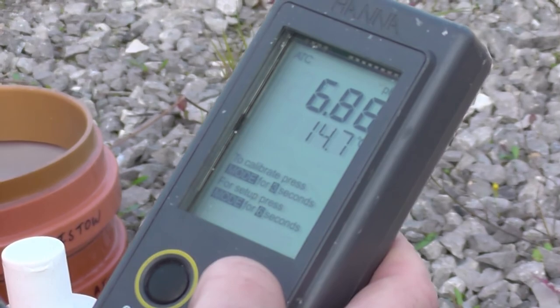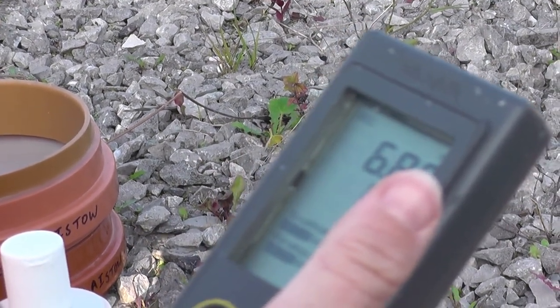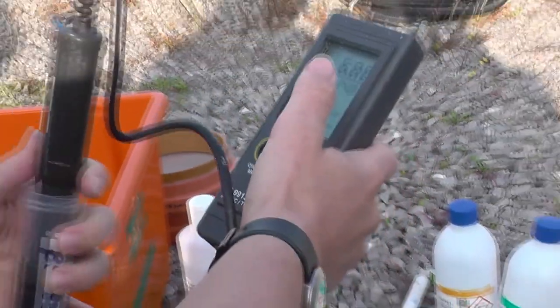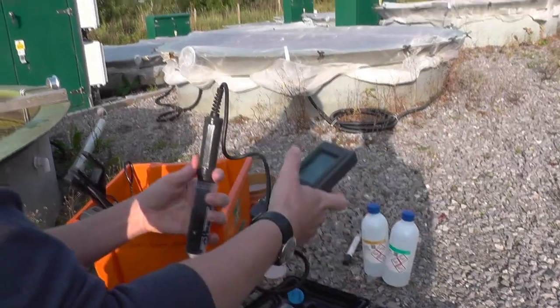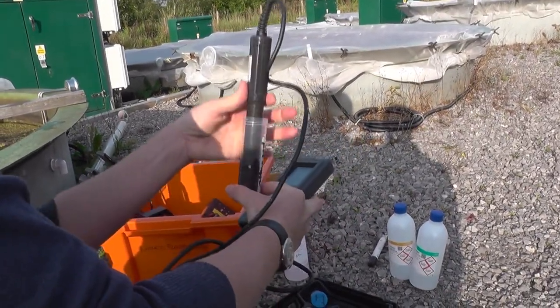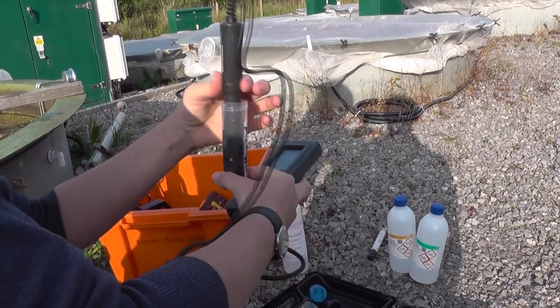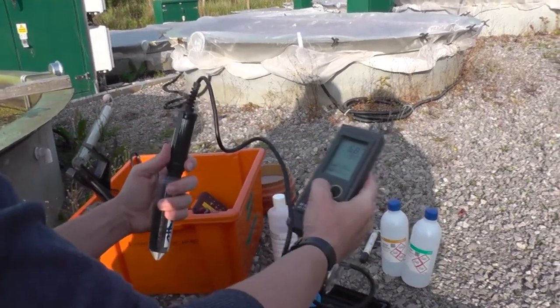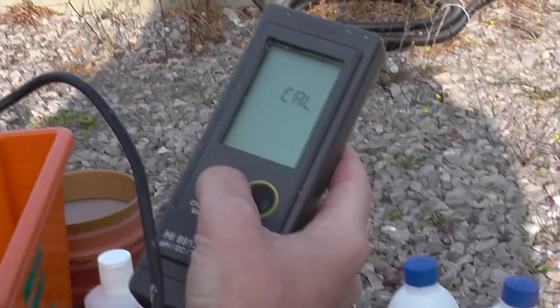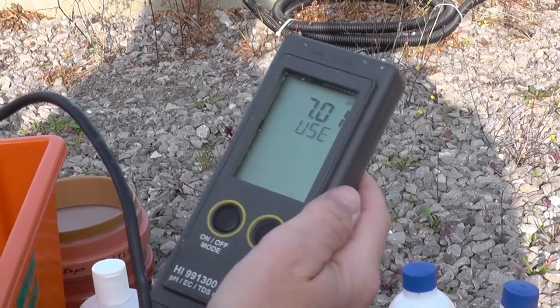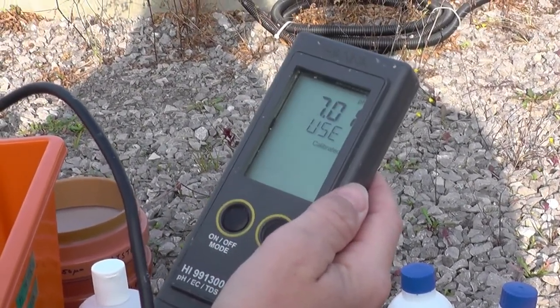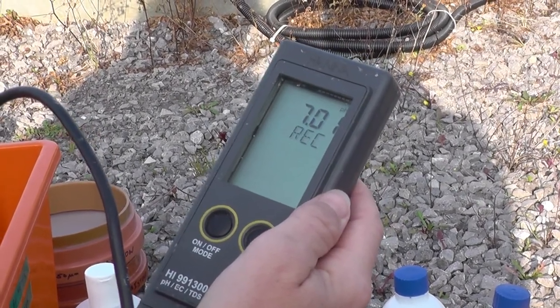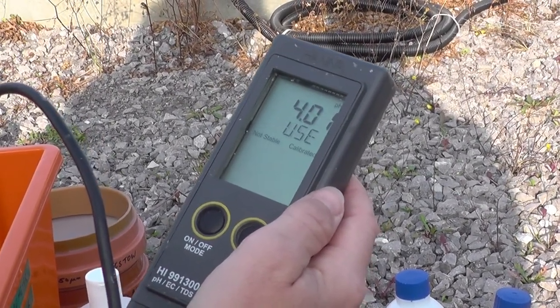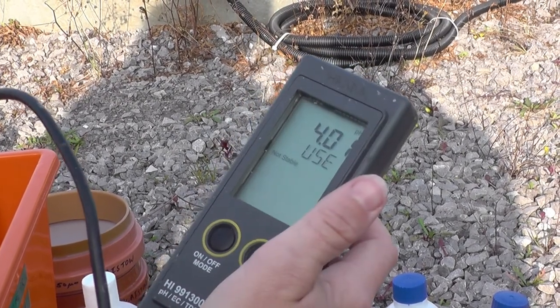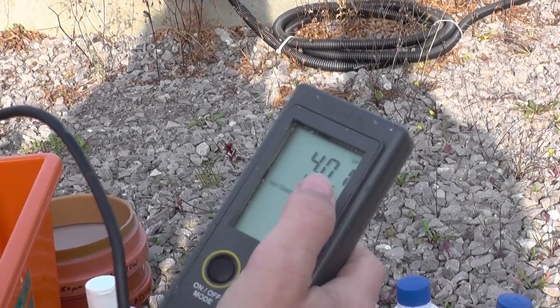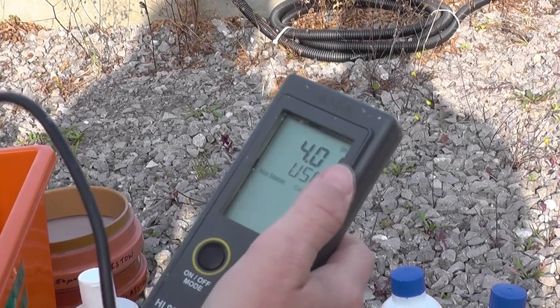Yeah, that's not quite right. It should be showing 7 up here. Sometimes it doesn't quite stabilize immediately because there's little bits of the RO water left on the probe. So we try and mix it around in here a little bit and try with the calibration again. So press this for 3 seconds again until it goes to cal mode. It's recording. Okay, so it has now recorded the calibration for the pH 7 buffer correctly.